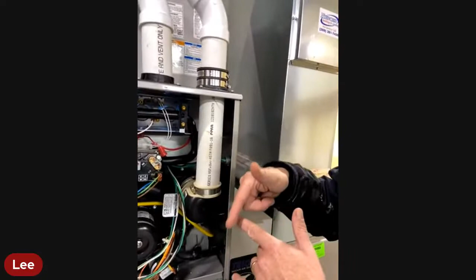Then it's going to have a glow stick or something along that line. You'll hear that click, gas runs through, fire's on. There's a little probe, hard to see, but it's basically a flame sensor, and sometimes it's a combination flame sensor and igniter. What that flame sensor is doing is just saying, yep, we've got flame, I can keep running, because if for some reason you don't have flame, you don't want gas spewing out.